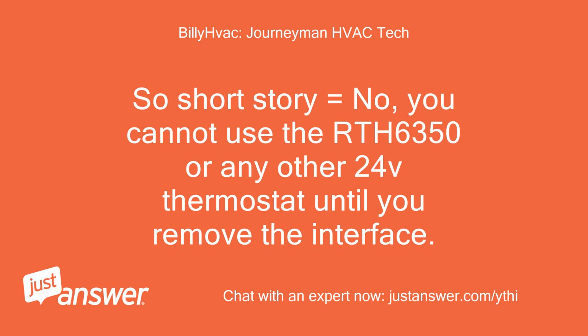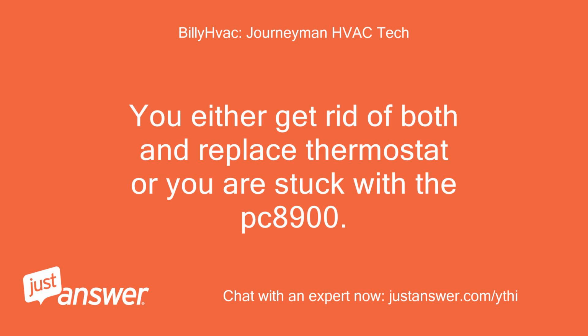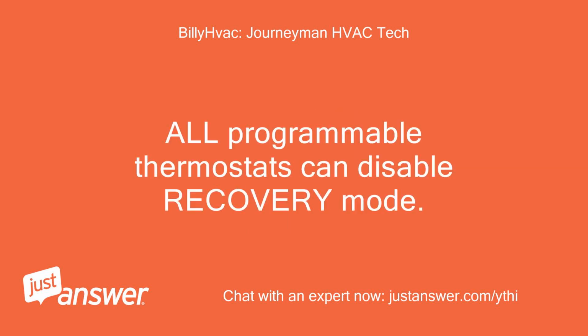So short story equals no, you cannot use the RTH 6350 or any other 24V thermostat until you remove the interface. Your thermostat and interface work as one unit. You either get rid of both and replace thermostat, or you are stuck with the PC8900. And all programmable thermostats can disable recovery mode.